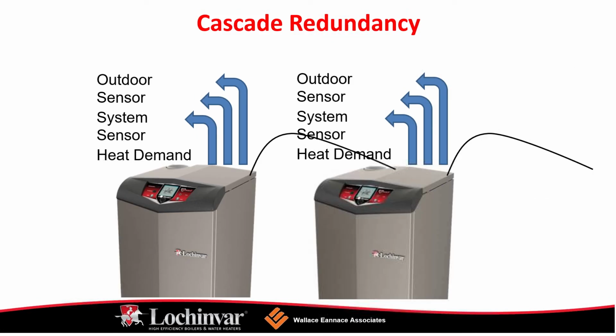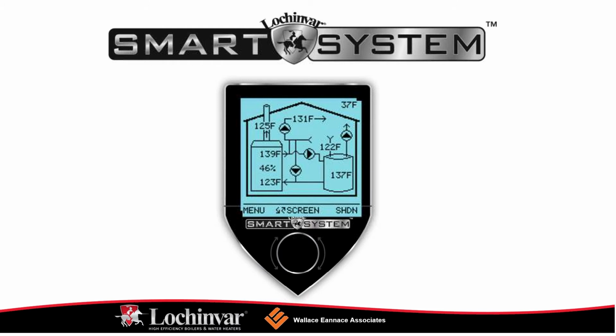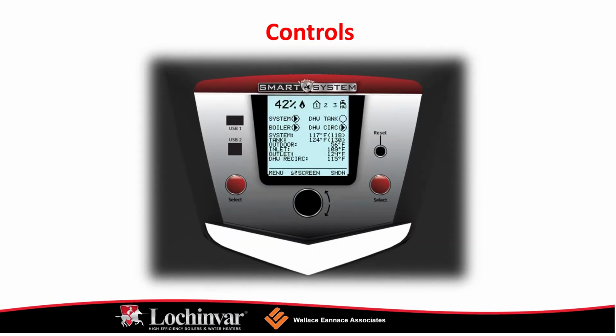Controls. Smart system controls is what Lochinvar refers to their control system as. Things like outdoor resets, outdoor air sensors, domestic hot water as priority, pump control, freeze protection, runtime and alarm contacts, high voltage, low voltage terminal strips, a time clock, data logging, a maintenance reminder, low water flow safety control and indication, and password security are all part of our smart system.